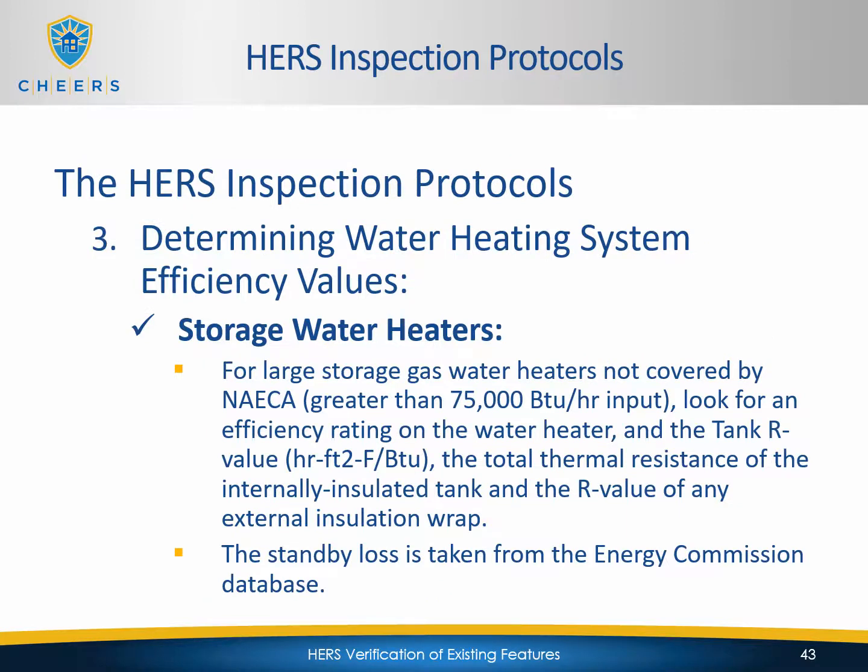For large storage gas water heaters not covered by NAECA, greater than 75,000 BTUs per hour input, look for an efficiency rating on the water heater and the tank R value, the total thermal resistance of an internally insulated tank, and the R value of any external insulation wrap. The standby loss is taken from the Energy Commission database.